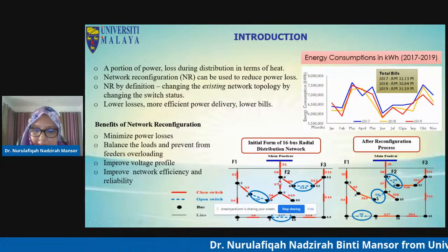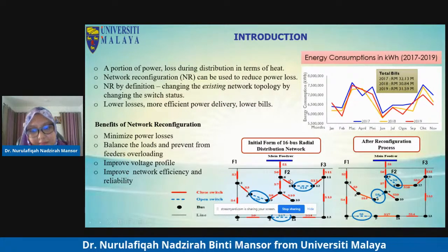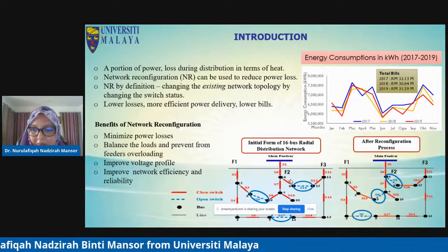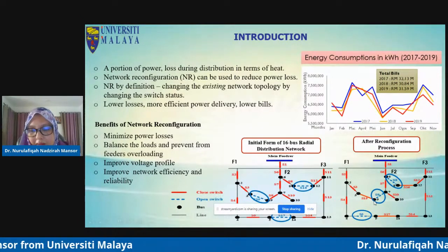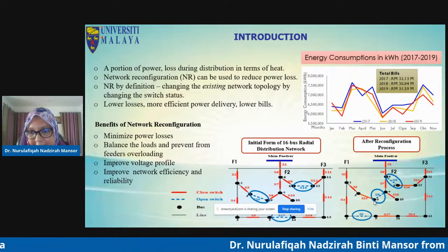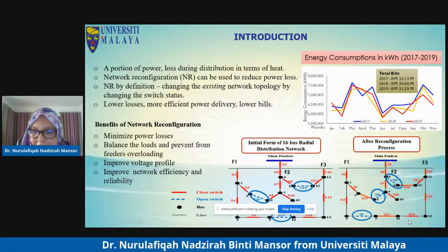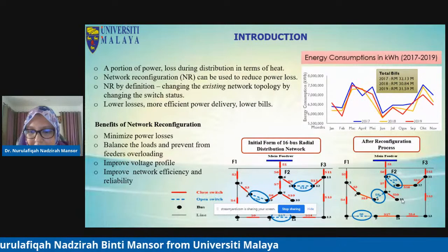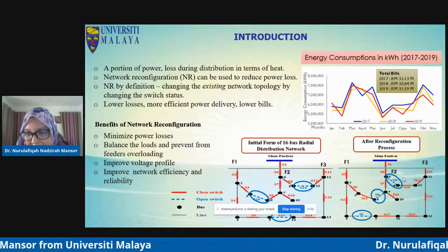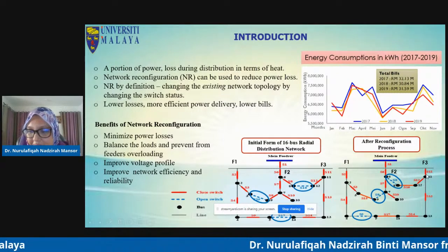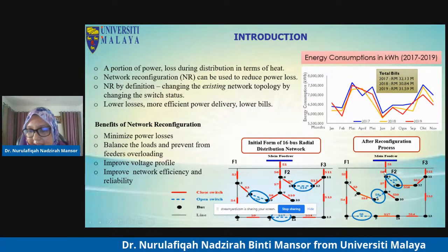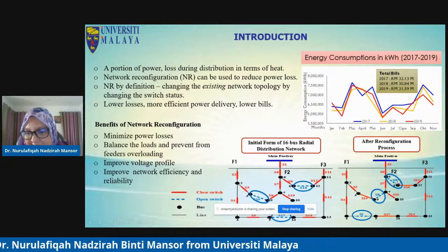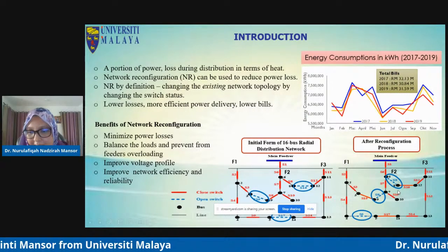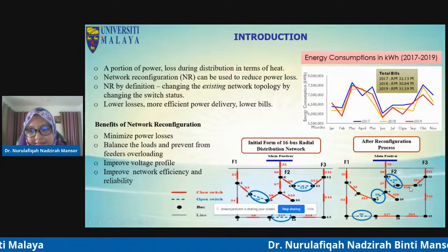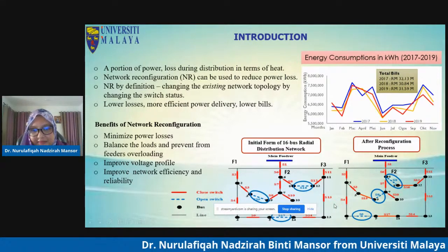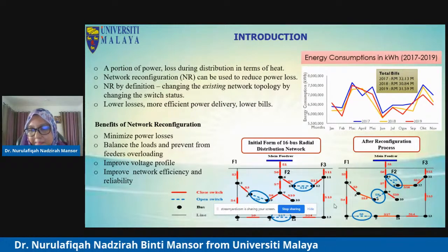After we model this network and optimize it with some criteria in mind, some objective function, let's say to minimize the power losses, we would obtain another layout like the one shown on the right. Now bus 5 and bus 8 are supplied from feeder 3 instead of feeder 1 and 2 previously. By opening switch 8 and switch 5, we transfer load 5 and 8 to another feeder. That is what network reconfiguration is: transferring load from one feeder to another by opening or closing a related switch.